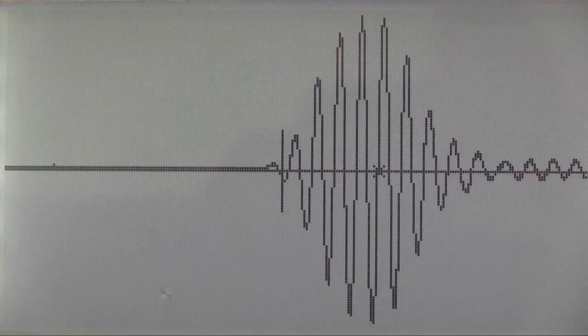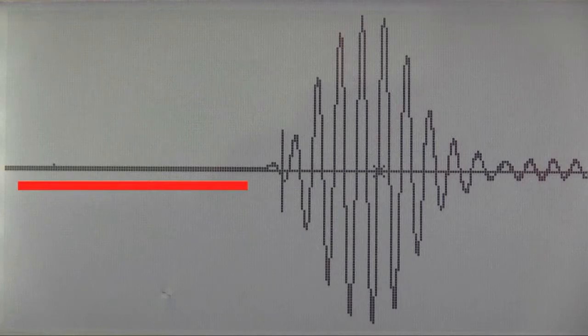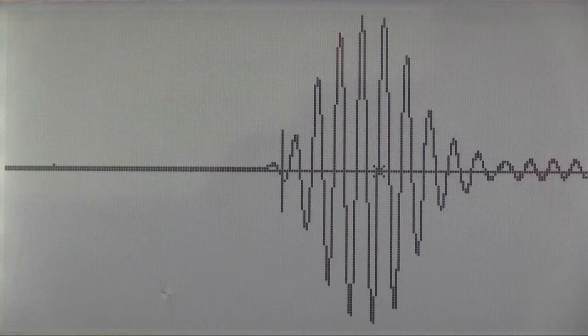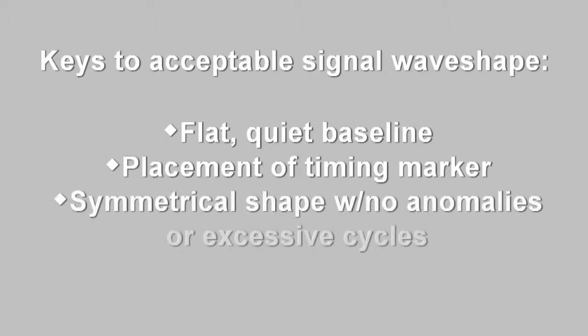When evaluating your signal, start from the left side of the graph. The baseline should be flat, leading up to the start of the wave. The wave shape itself should be symmetrical and reach maximum amplitude in typically five cycles, then begin to decrease again. Therefore, the keys to confirming an acceptable signal wave shape are a flat, quiet baseline, the placement of the timing marker, and a symmetrical shape with no evidence of anomalies or excessive cycles.